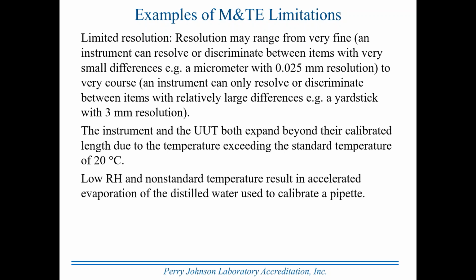Low relative humidity and non-standard temperature might result in accelerated evaporation of distilled water used to calibrate a pipette. So in certain laboratories, control of relative humidity would be critical, just as control of temperature is critical in a dimensional laboratory.